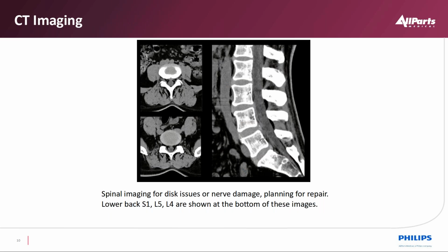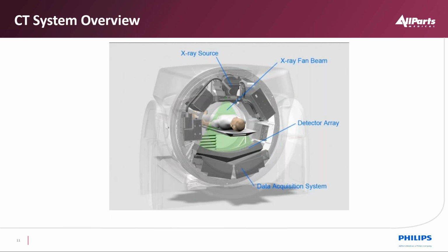So let's see, go back to this one. So we get into the CT scanner as we see it right here in this design. This is what's known as a third generation scanner. There were first generation, second generation, third, fourth, and even fifth. The generation is more of a topology of how we acquire the data. So a third generation in this context allows us to have multi-row detectors, and we spin all of this around the patient to build up at least a minimum of 180 degrees worth of data that we will then back project. 360 would be better, but a minimum of 180 degrees is required to produce an image.